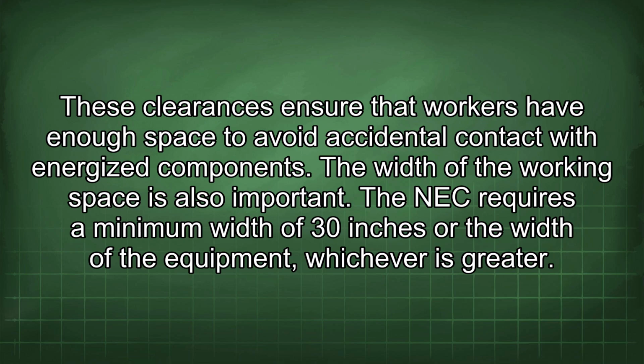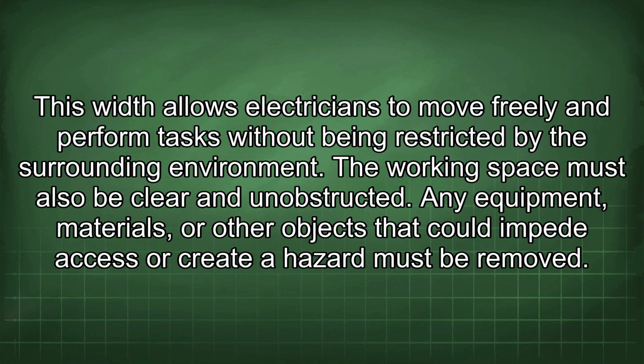The width of the working space is also important. The NEC requires a minimum width of 30 inches or the width of the equipment, whichever is greater. This width allows electricians to move freely and perform tasks without being restricted by the surrounding environment.